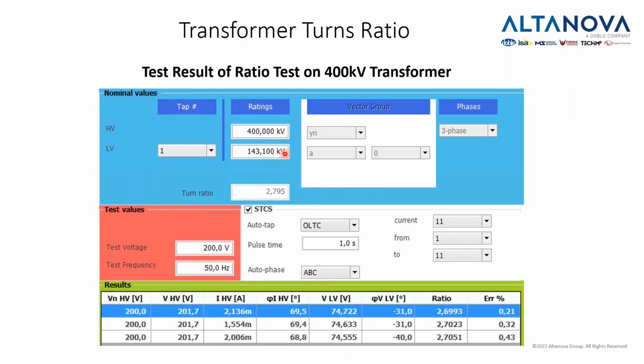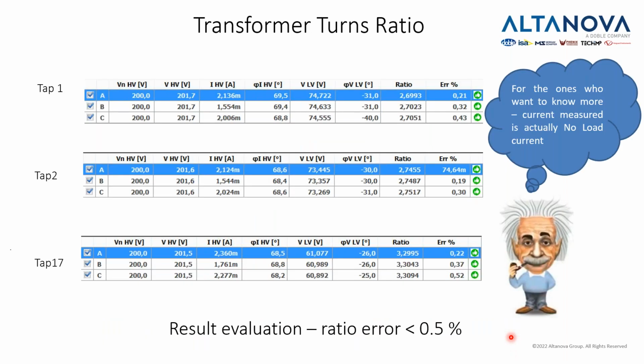And here is one example. We did a test on a 400 kV transformer, and we can see here the nominal ratio 2.795, and we have here the results 2.699, 2.7, 2.7, and the error of 0.21 to 0.43. Now, how do we know if we have a good result? The error should be lower than 0.5%, the error between the nominal value and the measured value of the ratio.